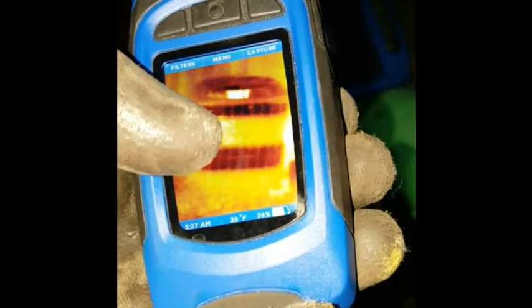gives you a nice view — you can see how the evaporator is pretty much only half full of liquid refrigerant. We've got these two big bands where the two fans have no liquid refrigerant. So just a quick scan with the thermal camera shows that this unit's low on freon.